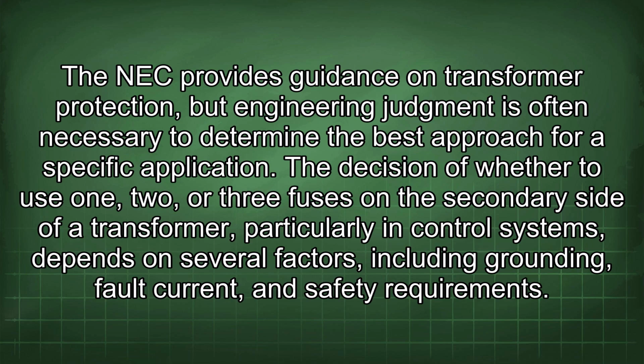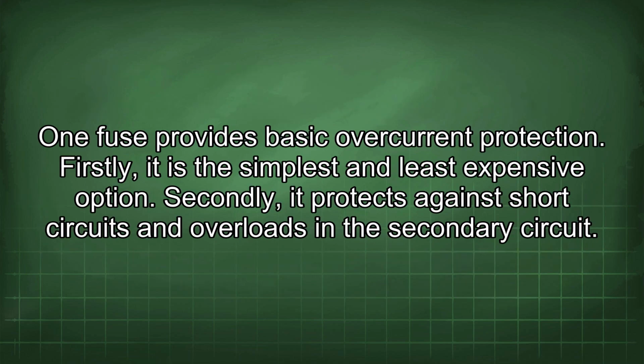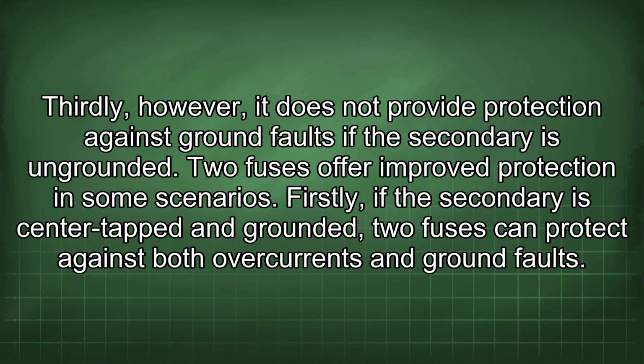The decision of whether to use 1, 2, or 3 fuses on the secondary side of a transformer, particularly in control systems, depends on several factors, including grounding, fault current, and safety requirements. 1 fuse provides basic overcurrent protection. Firstly, it is the simplest and least expensive option. Secondly, it protects against short circuits and overloads in the secondary circuit. Thirdly, however, it does not provide protection against ground faults if the secondary is ungrounded.